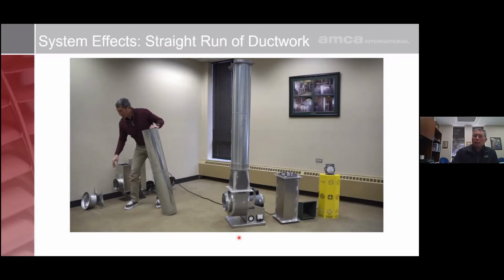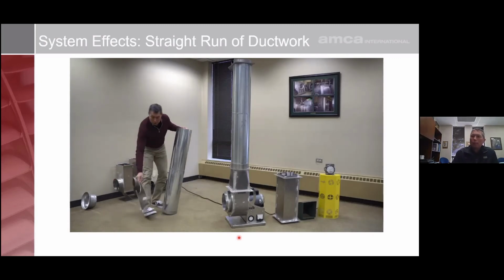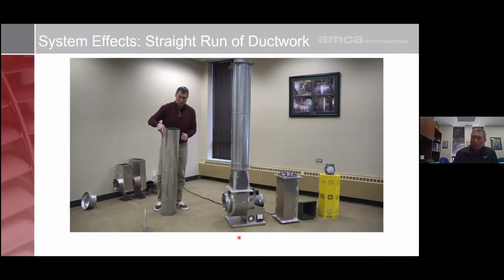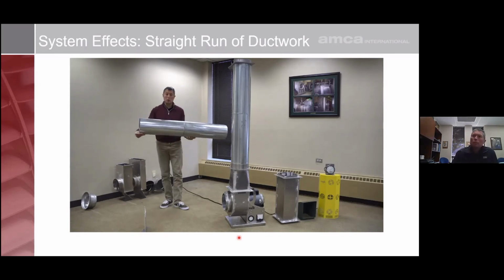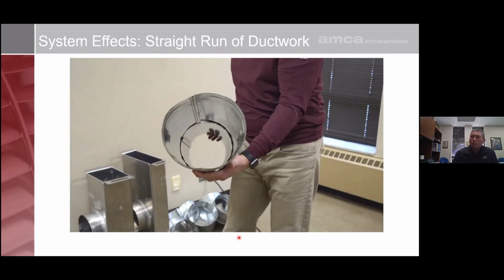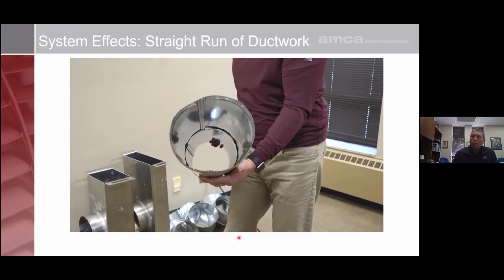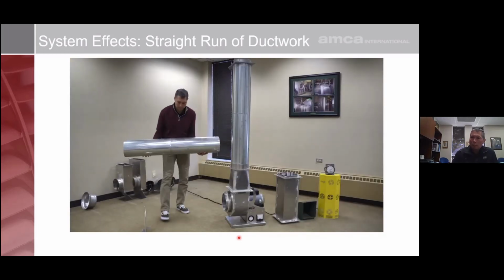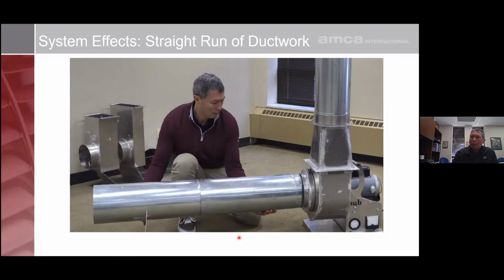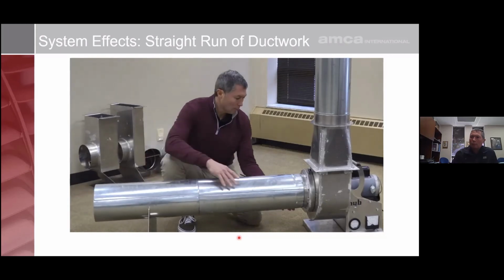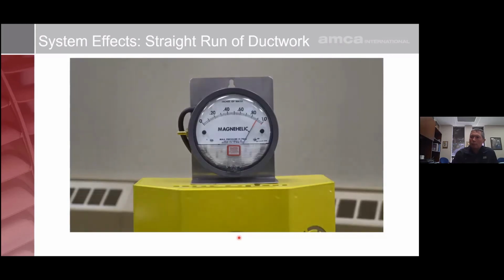Okay. Now the next piece of ductwork I'm going to add to the fan is just a straight run of ductwork. You can see that it's just a long tube, and there's nothing inside of the tube. It's just a very hollow piece, and we're going to see what happens. Putting this on the fan, you'll notice that there's a loss associated with this straight run piece of ductwork. And that loss is actually relatively significant.